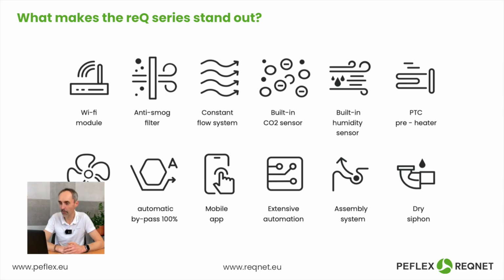A PTC-type preheater, which is essentially a sophisticated heater that automatically and precisely adjusts its power output to the current environmental conditions or specific demand, so that during the harsh winter periods it effectively protects the delicate heat exchanger from completely freezing, meaning preventing the blocking of crucial airflow, or even from potential and significant damage or total destruction.